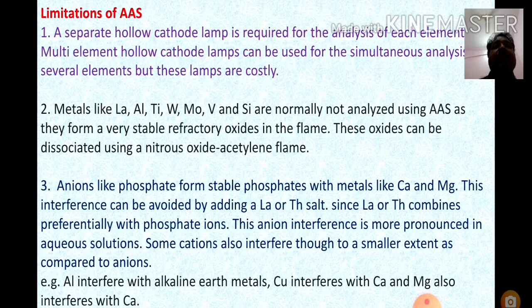Fourth limitation is that if two elements in the sample absorb at the same wavelength, then their simultaneous analysis becomes difficult. For example, manganese and gallium, they both absorb at 403.3 nanometer. Therefore, this interference can be avoided by extracting out the interfering element using chemical separation technique.